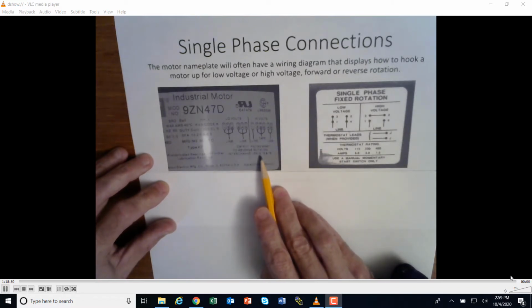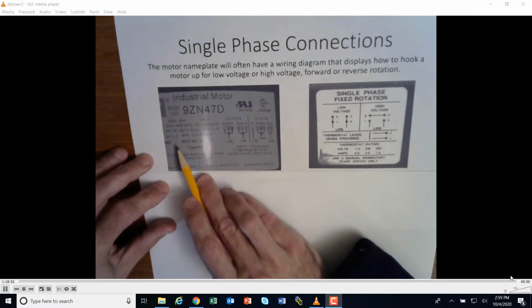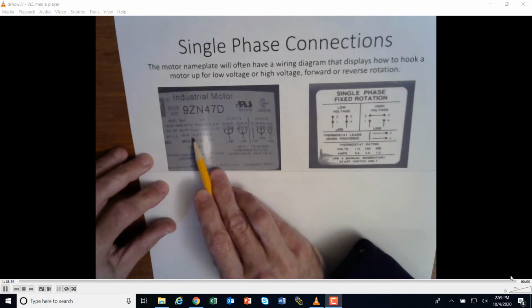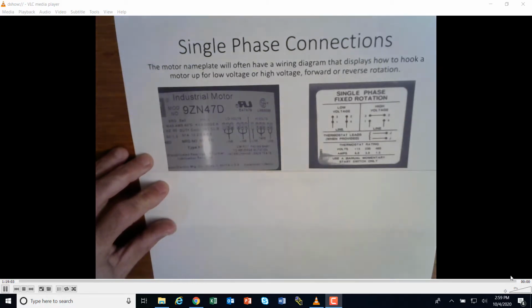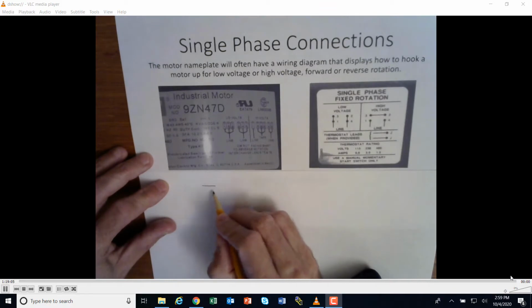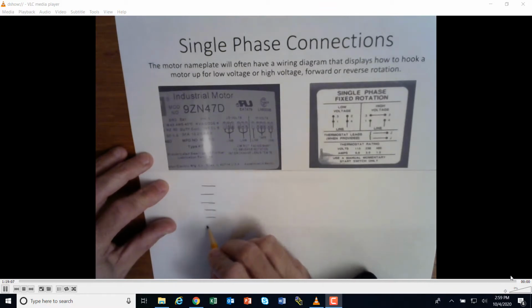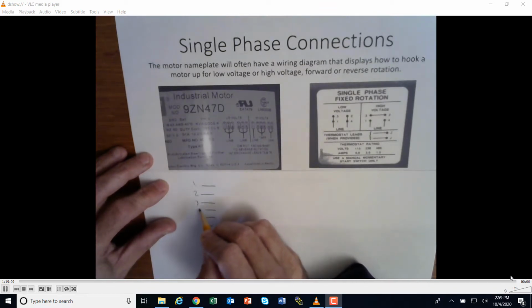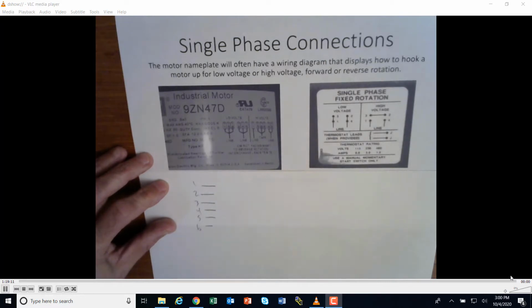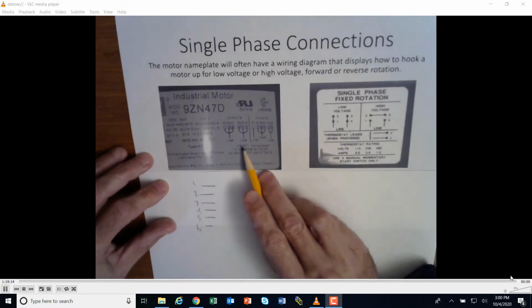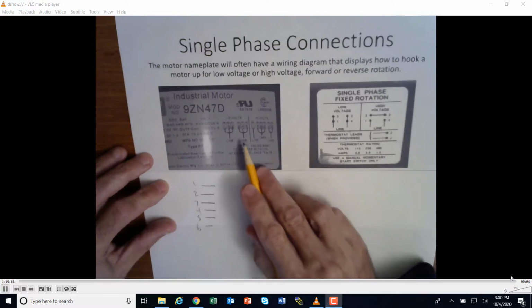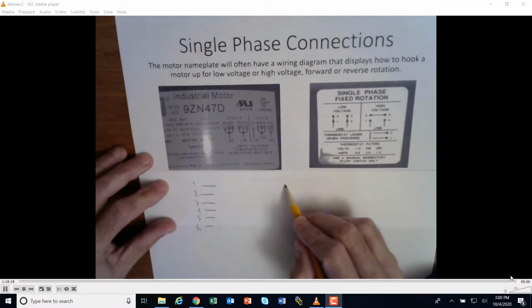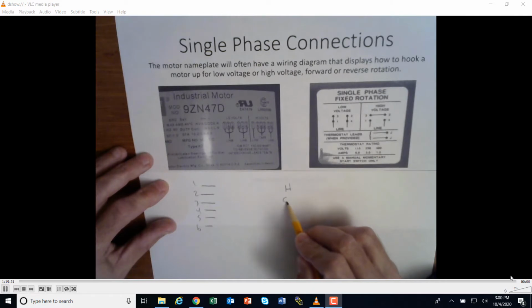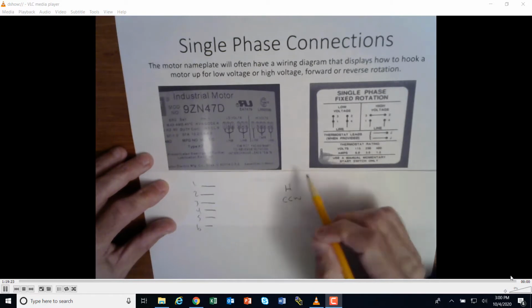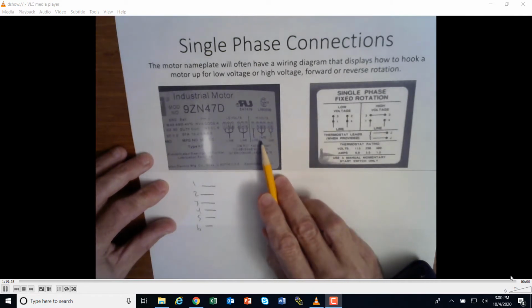All right. The nameplate here tells me that I have a service factor of 1, so my service factor amps are 13.2. So if we wanted to go ahead and wire this up, you're going to see 6 wires coming out of the motor. Okay. And if you wanted to run, let's say, counterclockwise, and you wanted to run high voltage. So let's say we're going to run high voltage and we're going to run counterclockwise. Okay. So we'd be looking at this chart right here.